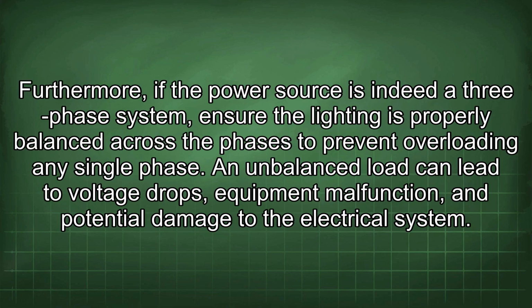Furthermore, if the power source is indeed a three-phase system, ensure the lighting is properly balanced across the phases to prevent overloading any single phase. An unbalanced load can lead to voltage drops, equipment malfunction, and potential damage to the electrical system.